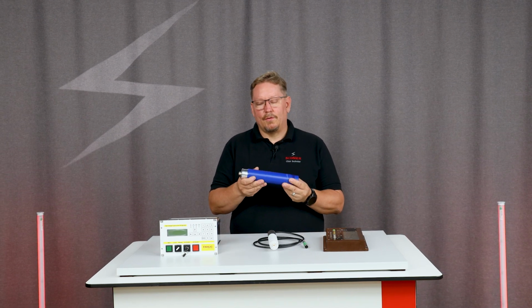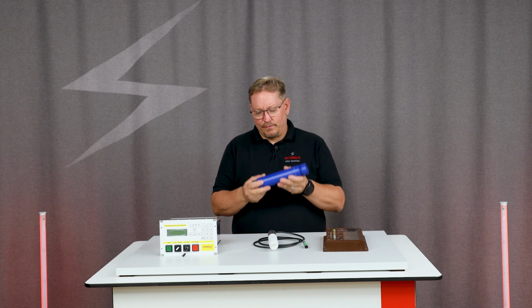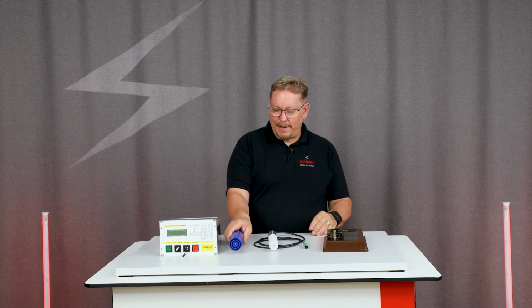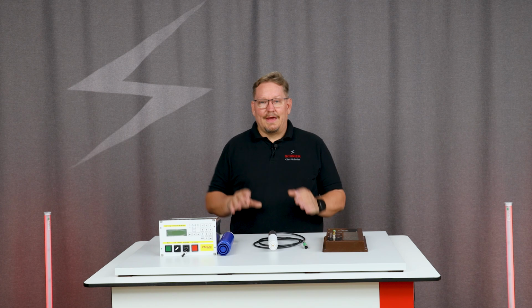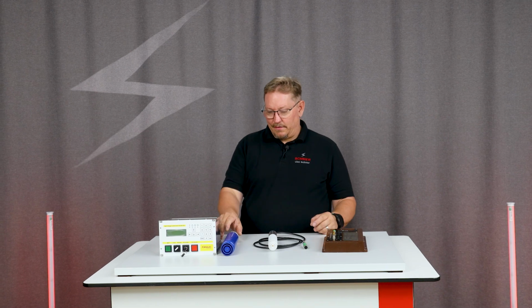If the installation is not done properly, if there is moisture or dirt on it, then that can lead to problems. And no matter how, even if we integrate the high-voltage generator into the atomizer, we are still in the ignitable range. Because if we want to be outside the ignitable range, then we have to comply with 0.24 millijoule.